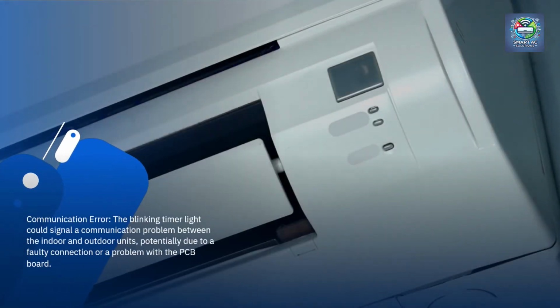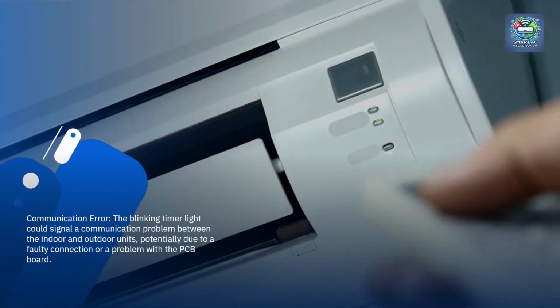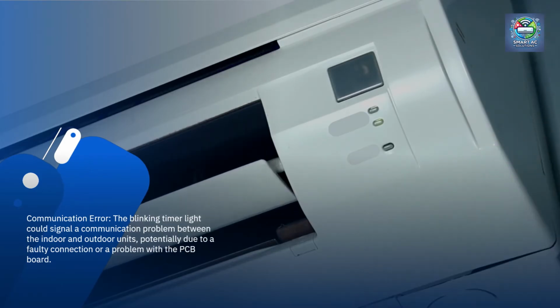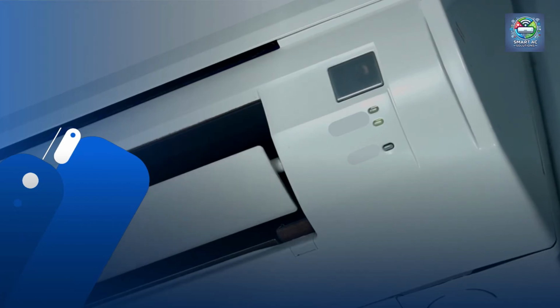Communication error. The blinking timer light could signal a communication problem between the indoor and outdoor units, potentially due to a faulty connection or a problem with the PCB board.